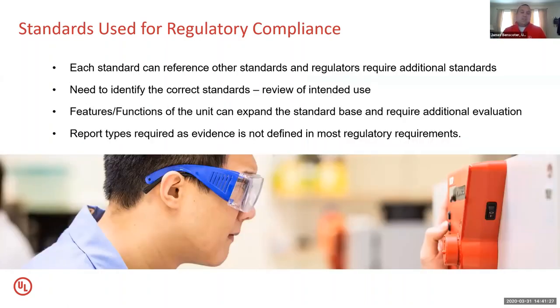Really, when we get into these specific standards, they can reference other standards. So if you were to look at the EUA for ventilators, for example, you'll see a reference to a standard IEC 60601, which is used as the basis for ES 60601. Within that standard itself, it will make reference to other standards, such as IEC 62304 for software development, and that is found in clause 14.1 of the 601 standard. So you can start to see in the EUA for ventilators, you'll see the 60601 standards, and then you'll see this reference to 62304. In this case, it already was inferred based on the base standard. However, they still felt it was necessary to call it out.